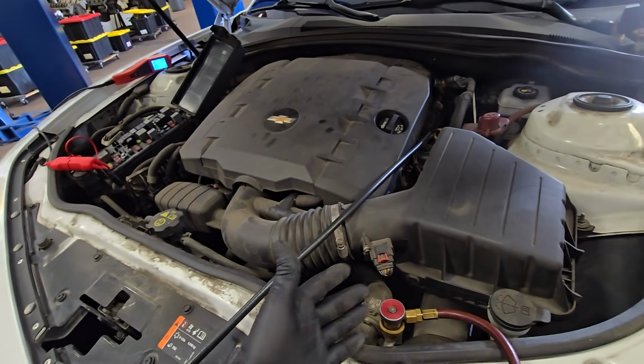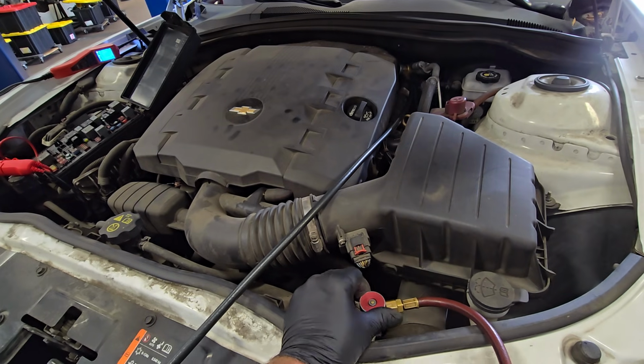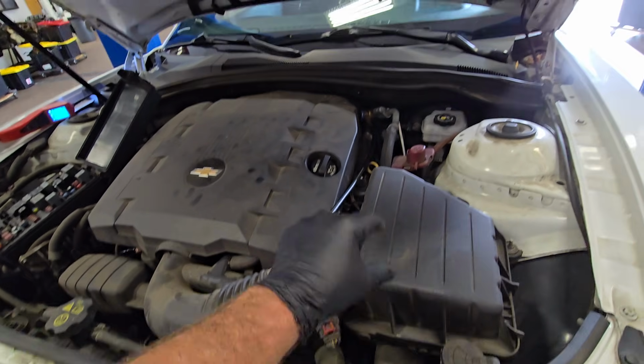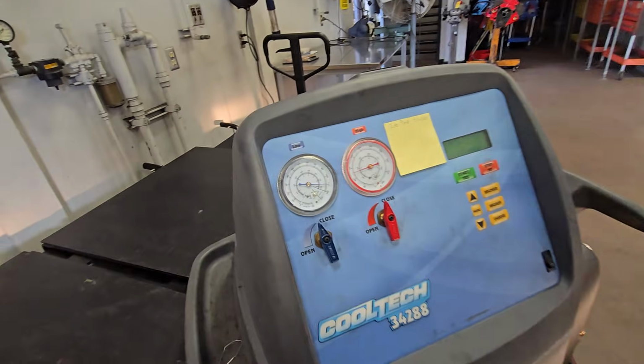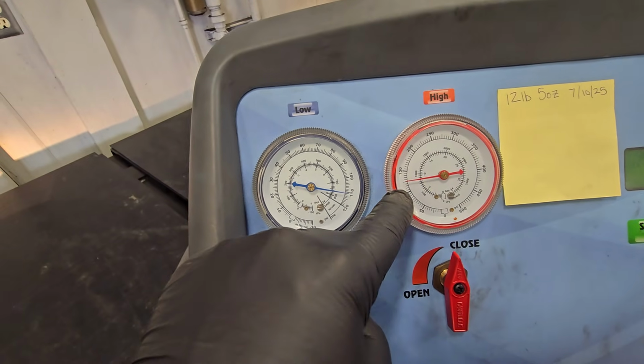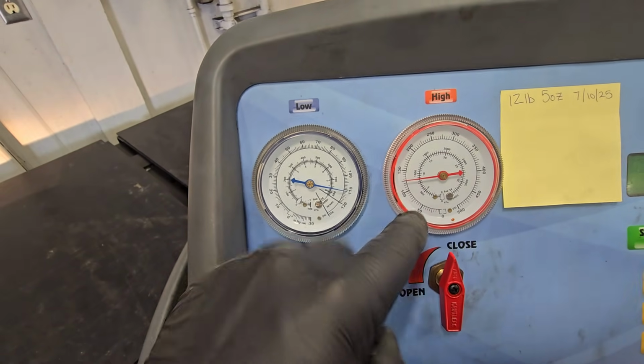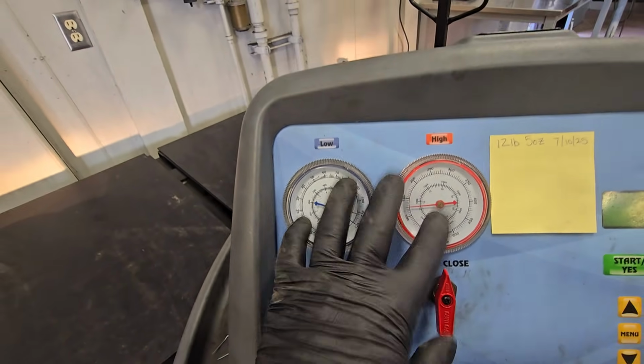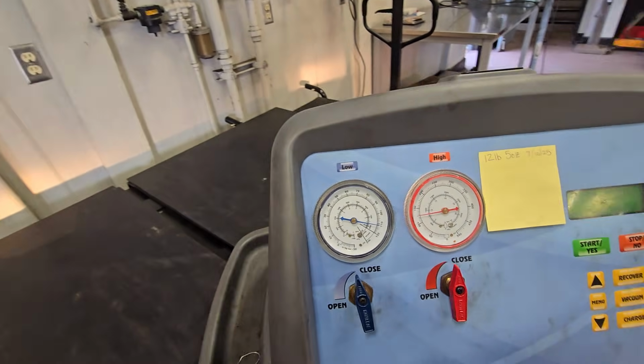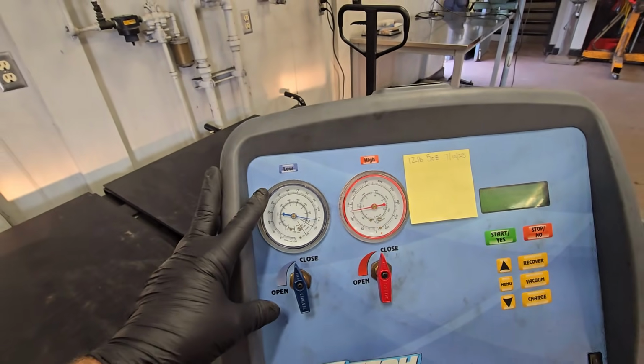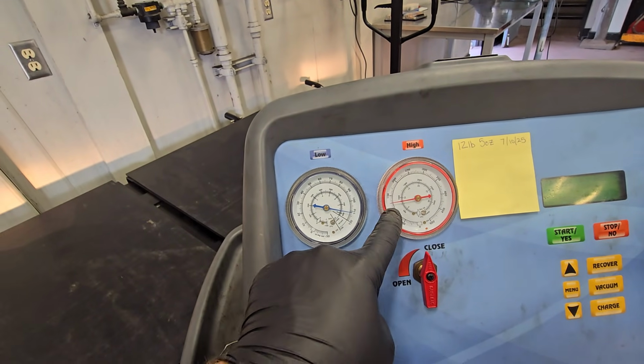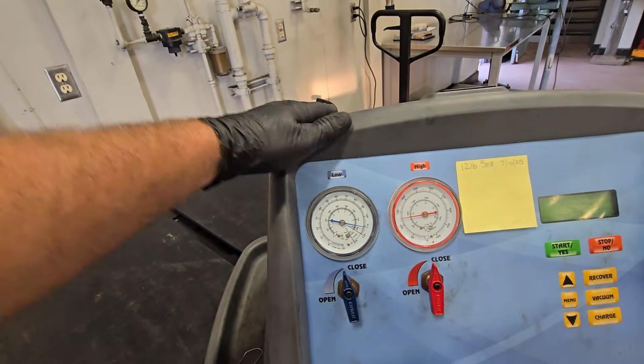However, just to be thorough and to demonstrate what I could do, I could hook the high and low side up and get a pressure reading of 110 and about 120 - they're going to be about the same. So both of these are reading 100 and something. Because it's pretty hot, that reading right there indicates the system is full.